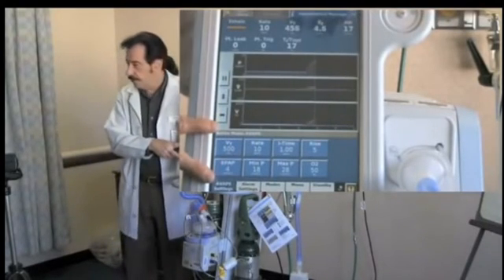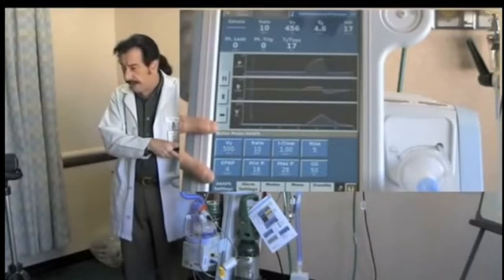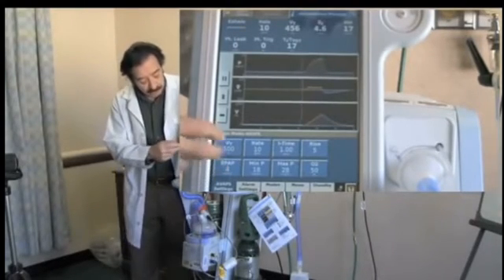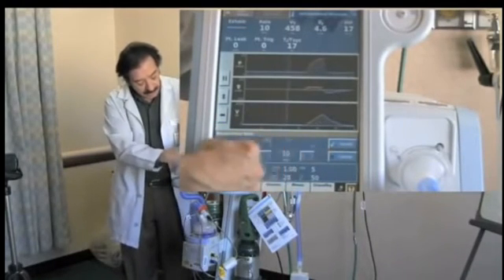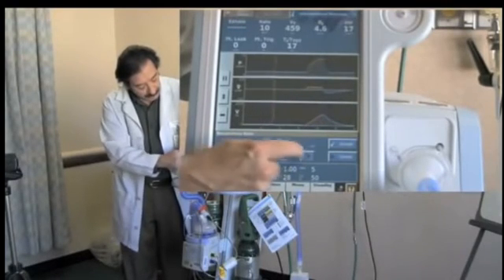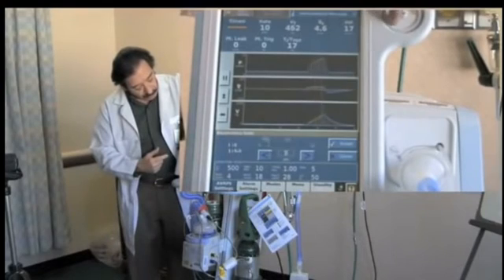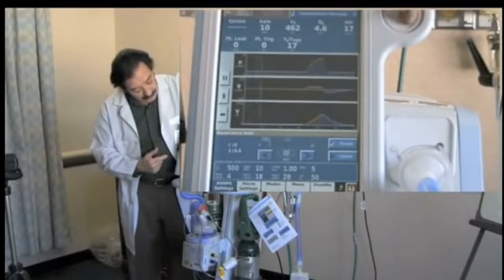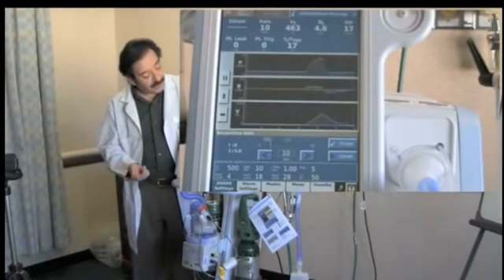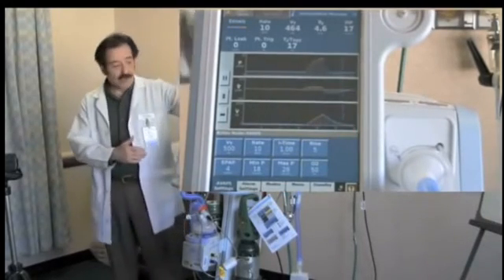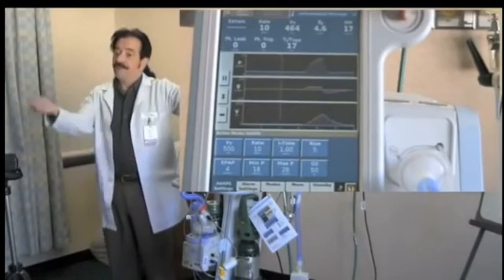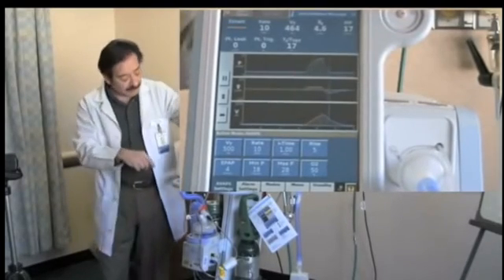The next panel is your parameter, your user-defined settings. And there's two ways to make settings. You can either touch the button, which activates the adjustment, and go up or down here with the adjustment buttons, or you can use this scroll wheel and then confirm. You have to confirm the change by either hitting the green check mark here or the accept button here. Okay, and then that accepts the change. If you don't acknowledge the change you've made, then it reverts back to what it was set at. It never completes the change.